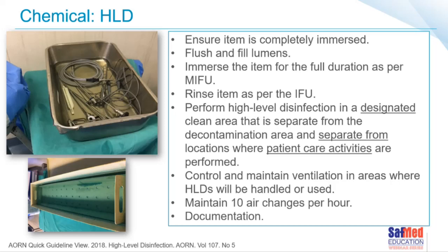Ensuring that the item is completely immersed, flushing and filling the lumens, immersing it for the full duration as per the manufacturer's instructions for use, as well as not immersing it for longer than what is recommended. Rinsing the item as per instructions for use. There are some OPAs at one point that had an IFU that said 3 separate rinses. Perform high-level disinfection in a designated clean area that's separate from the decontamination area and separate from the locations where patient care activities are performed.